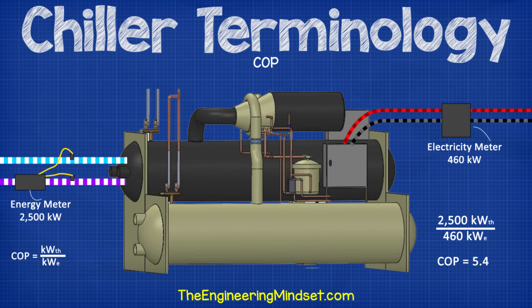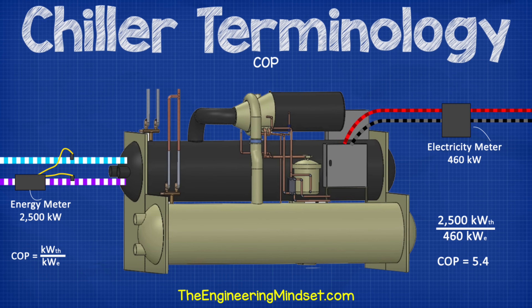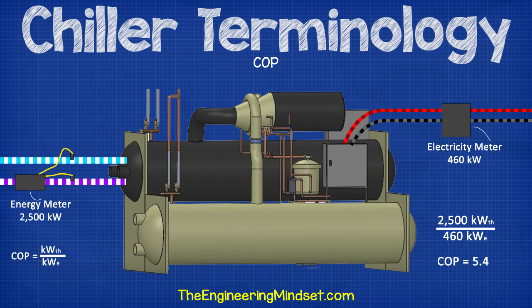COP. COP stands for the coefficient of performance. It's simply a ratio of how much cooling you get per unit of electricity you put in, which is a way of measuring the chiller's efficiency. To calculate COP, it's simply the kilowatts of refrigeration divided by the kilowatts of electricity. For example, 2,500 kilowatts of cooling divided by 460 kilowatts of electricity equals a COP of 5.4. So for every 1 kilowatt of electricity you put into the chiller, it will generate 5.4 kilowatts of cooling. It is useful for measuring the efficiency at a specific point in time under specific conditions.